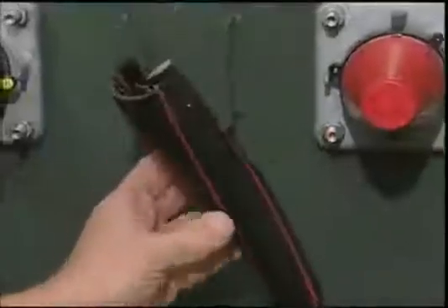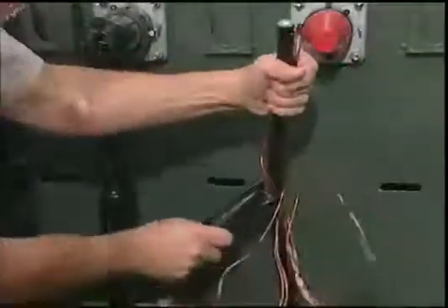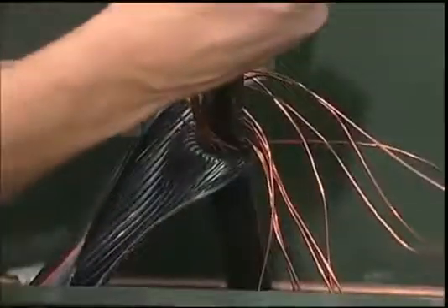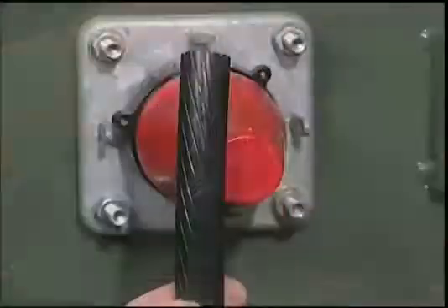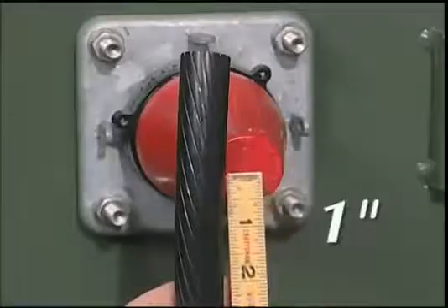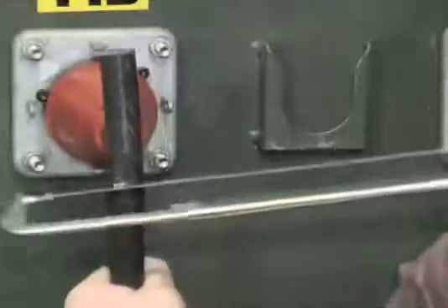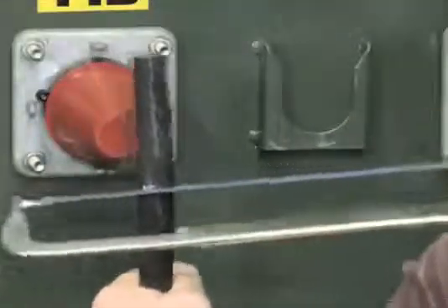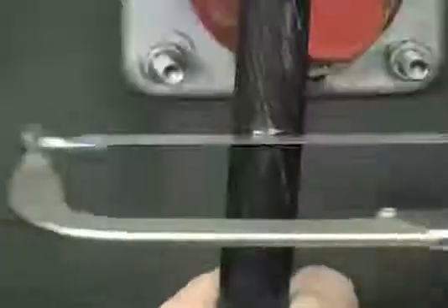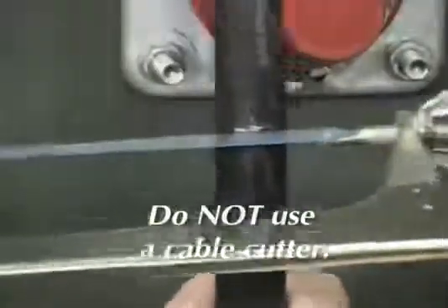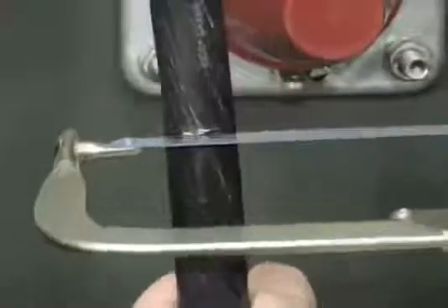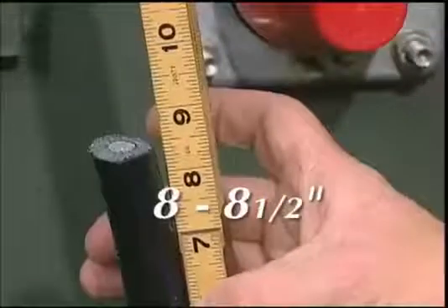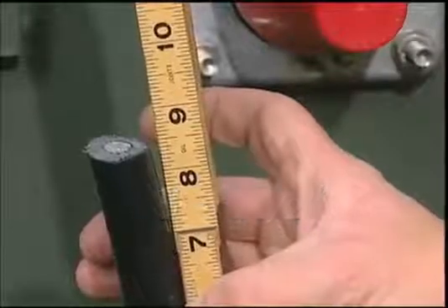Peel back the insulation. Unwind the neutral wires, bend them down, and secure them temporarily. Measure 1 inch from the center line of the bushing insert. Cut the cable using a hacksaw to make a straight cut. Do not use a cable cutter, which usually just can't make a straight flat cut across the cable. Ensure that 8 to 8.5 inches of the insulation shield is exposed.